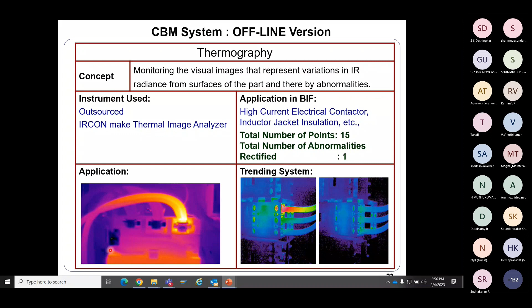That is more important. When the system is live, you can see the color change, based on which you can call for a shutdown and then attend to it immediately. This is a thermal image analyzer which can be deployed, and these are predominantly used for a thermography condition-based monitoring system.